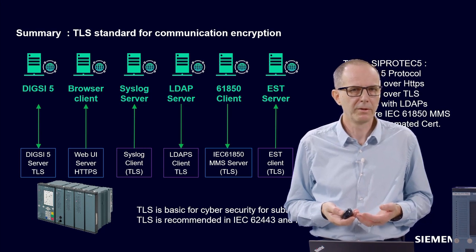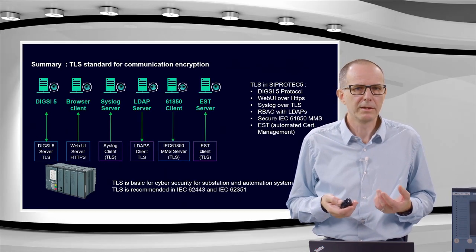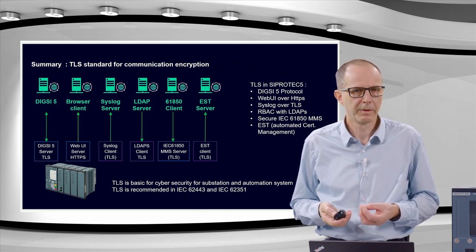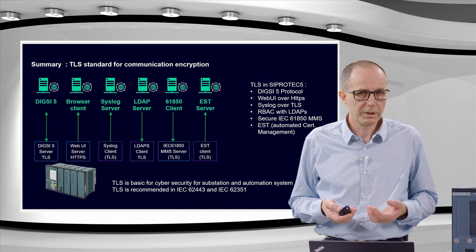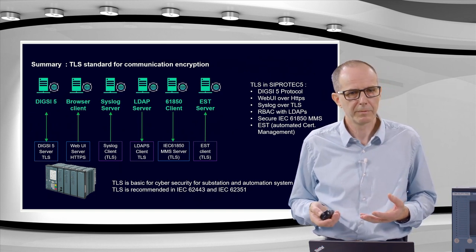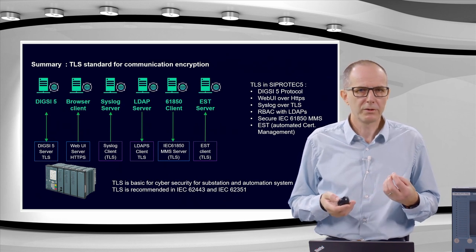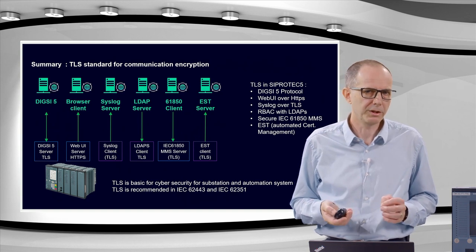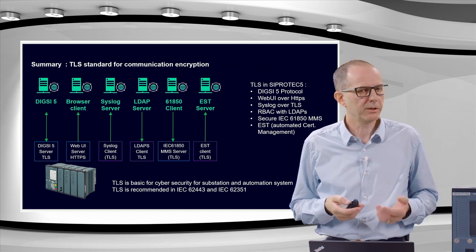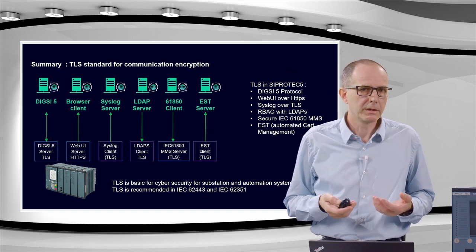Why should we talk about TLS? Because it's used as a state-of-the-art method for encryption. And we have implemented this everywhere in SIPROTEC 5 where data integrity is necessary. For the engineering tool DIGSI, the communication protocol is encrypted via TLS with mutual authentication. For the access to the web page, HTTPS is encrypted via TLS with server authentication. In case syslog messages want to be protected from manipulation, TLS can also be applied.